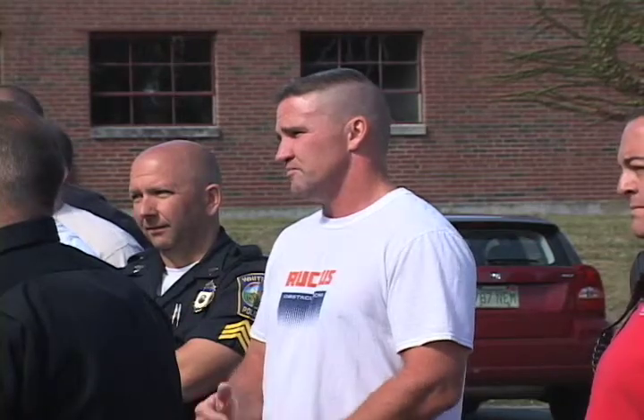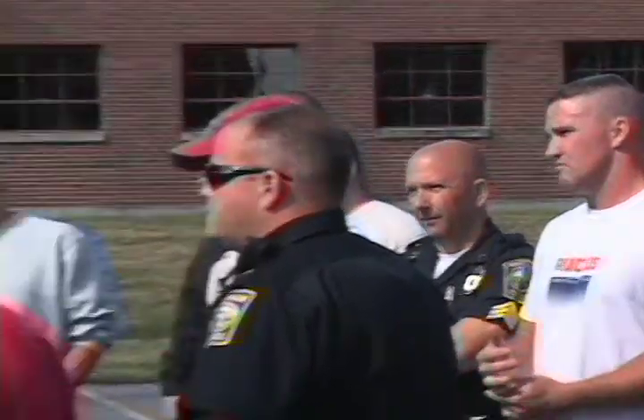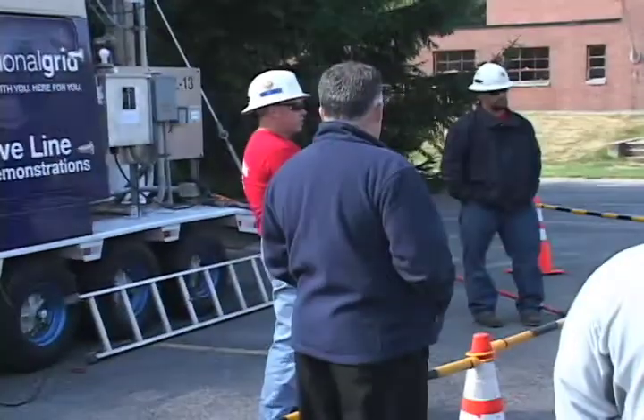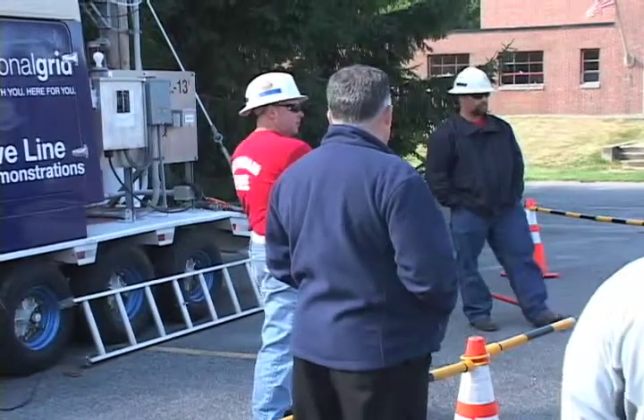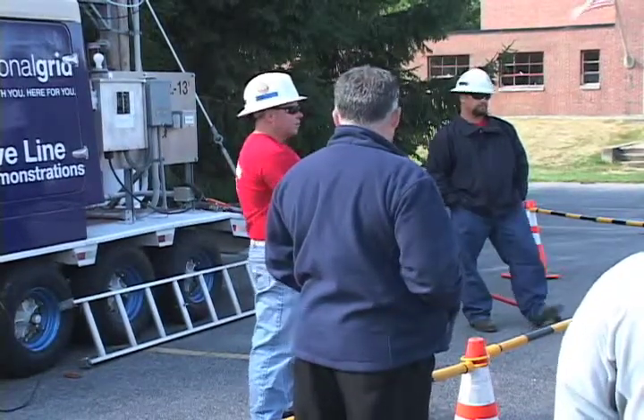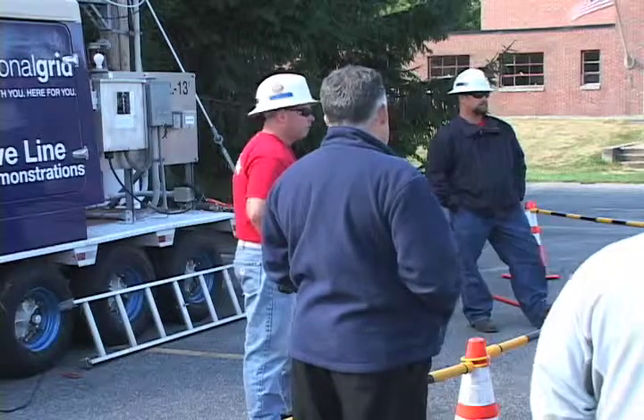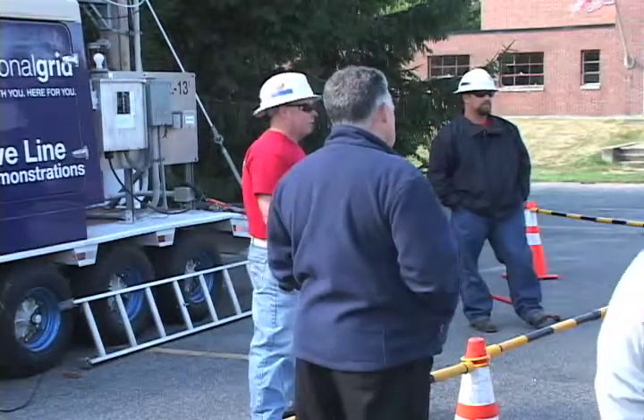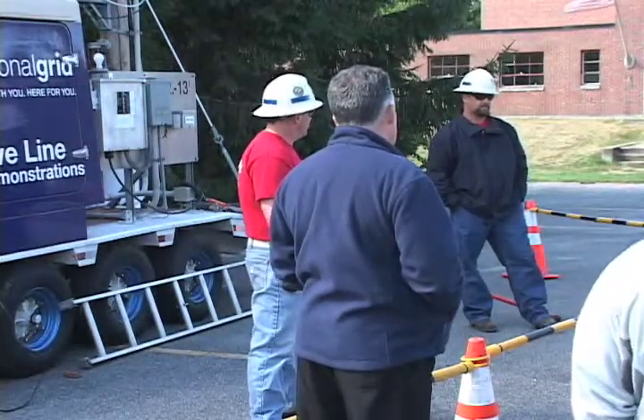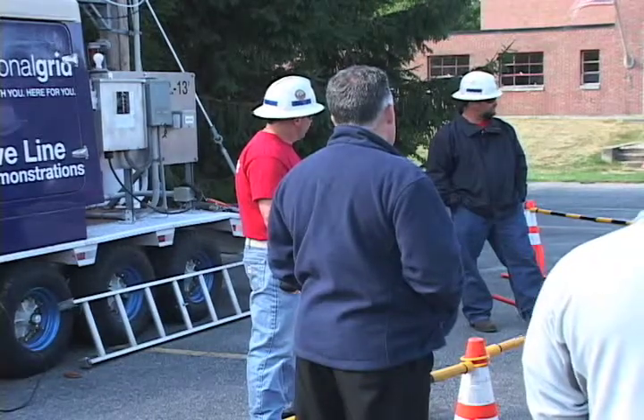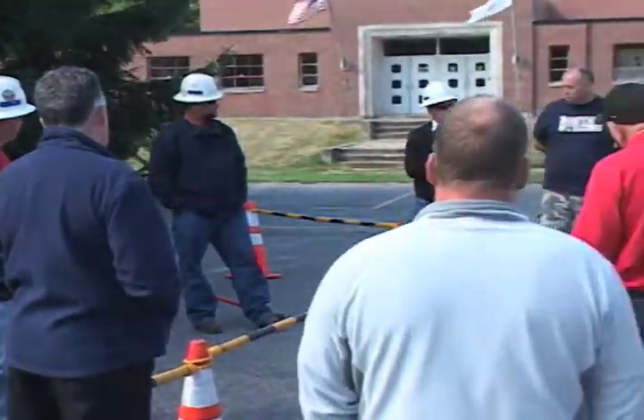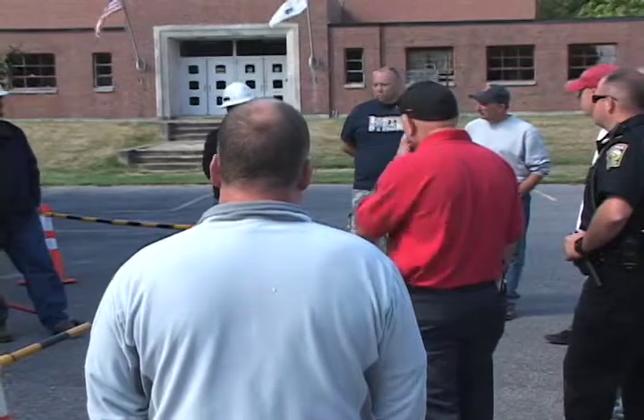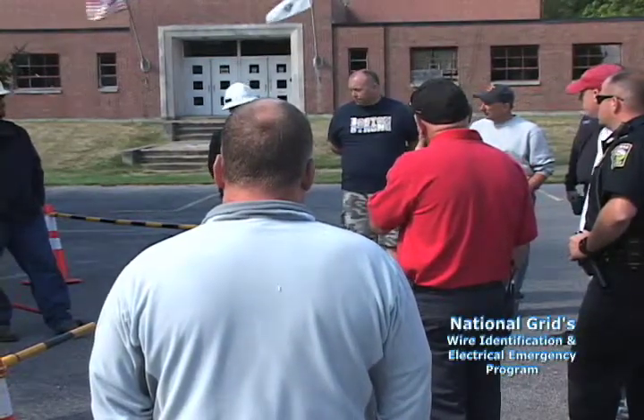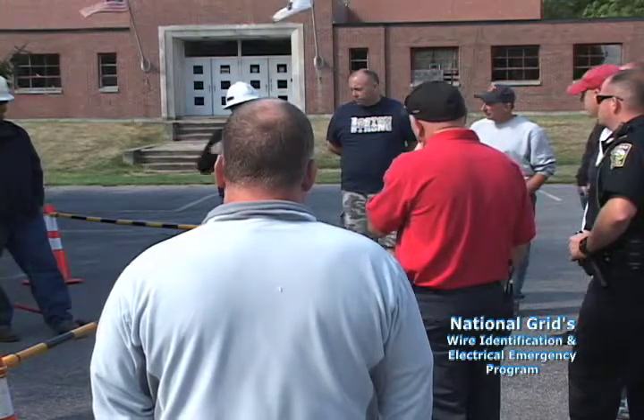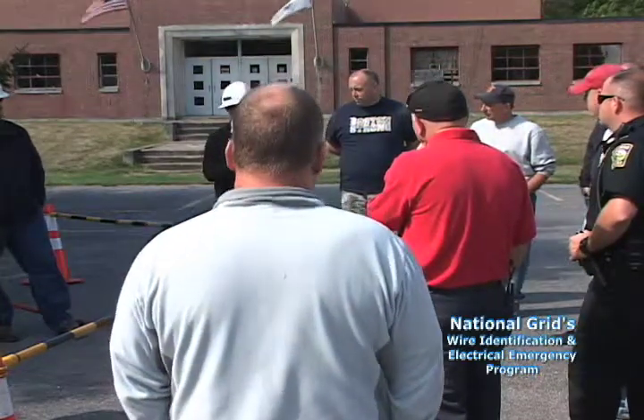Right, there's the inverter, it needs to see utility power to put it on the line. As soon as it loses utility power, it opens up and doesn't allow it to pump out on the line. So they'll still be able to power their own house, but not out to the grid? They can't power their own house either. In order for them to power their own house, they'd actually have to have battery sets inside. Short of that, they disconnect themselves off, and the utility power has to come back on for 5 minutes before it's able to come back on and actually supply power back to the house.